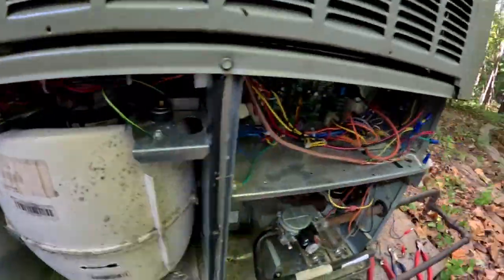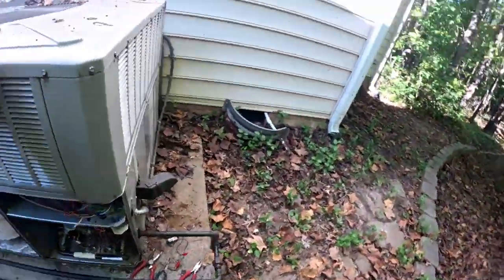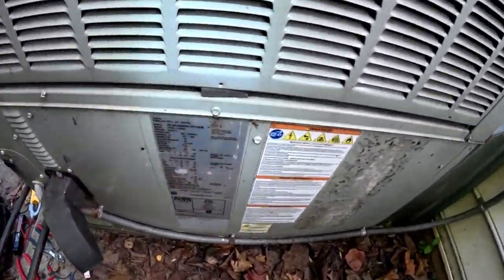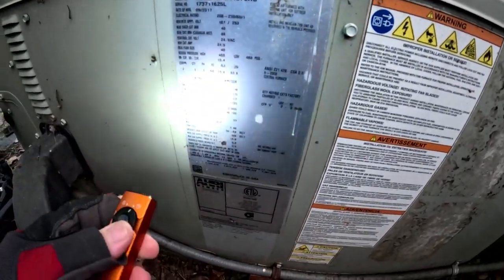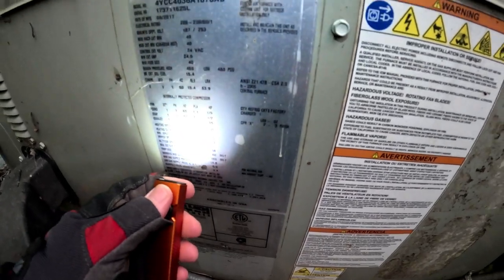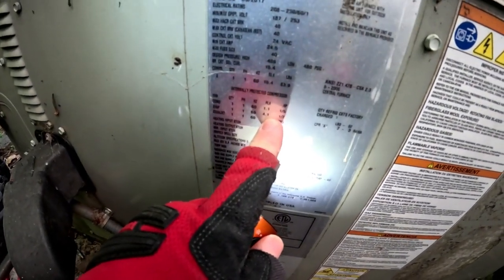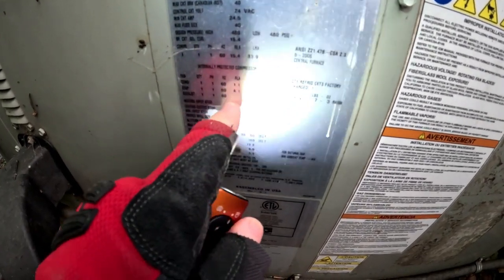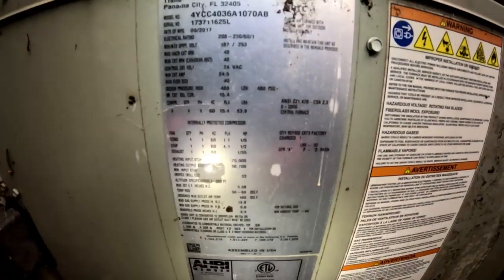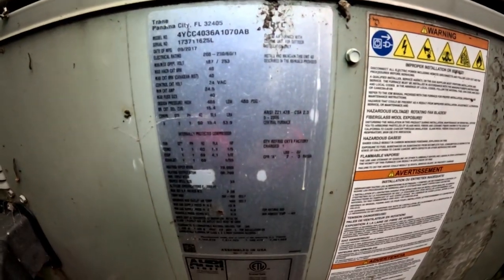So as you know, the sticker is always covered by the belly band. If you want to get any kind of amp draw or information off of it, you got to tear all that apart. And they usually, let's see, fan, condenser, evaporator. Full load amps on this is 4.1, so it is on the side of the package unit right there. You see that? So our full load amps is going to be 4.1 on that evaporator motor, so half horsepower. And we're about 2.8. So our amp draw is below what the full load is on it.